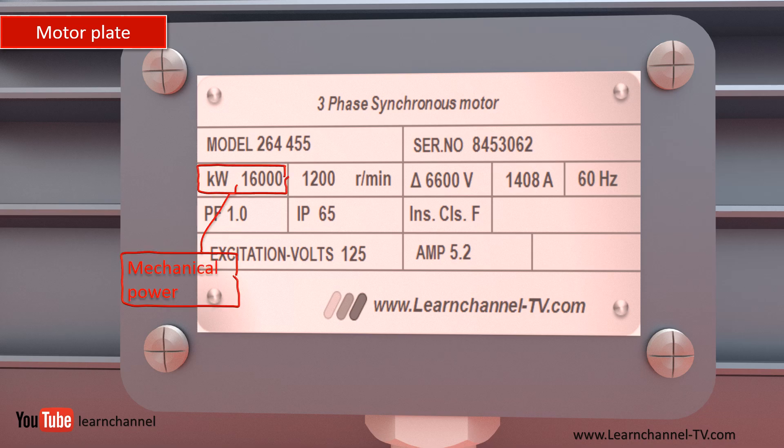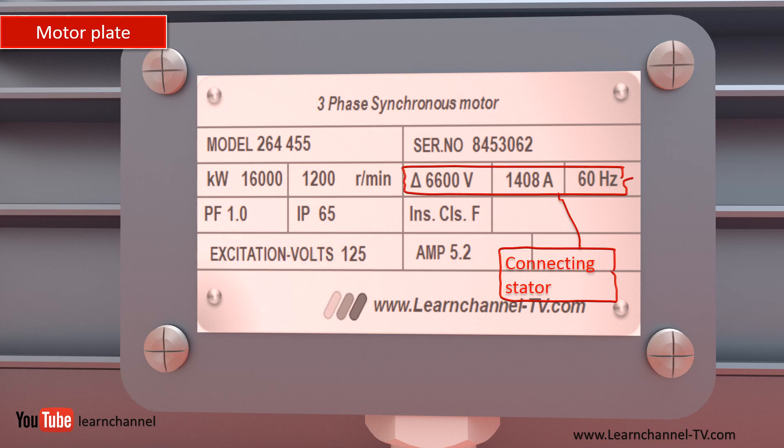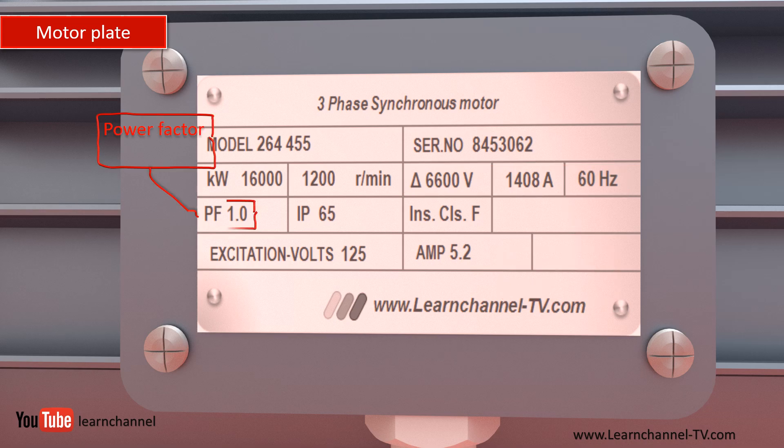The motor's rated mechanical output power is given in kilowatts. The motor's rated speed, or full load RPM, refers to full load. This electrical data is important for the stator windings. Here, you can connect the motor in delta. Note that the power factor at rated operation is 1.